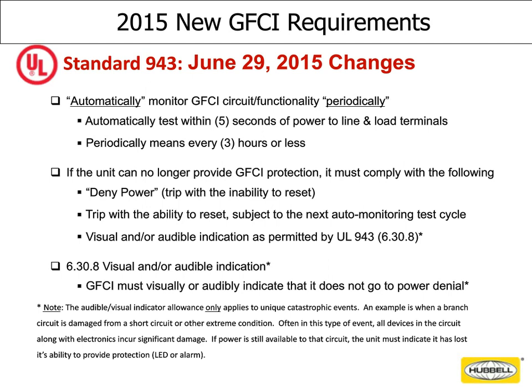So on June 29th, every ground fault that exists must be self-testing, and it must also deny power in the case of detecting a problem. So every unit now has a microprocessor built into the ground fault. It runs a circuit test, checks for functionality, and tells the user if there's a problem. So you'll see here in section 6.30.8, every ground fault must have either a visual or an audible indicator. In the case of a Hubbell ground fault, you now have a microprocessor. It's checking the circuit every minute. It's checking to make sure that ground fault is protecting.